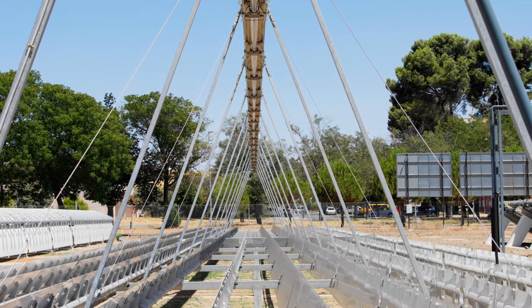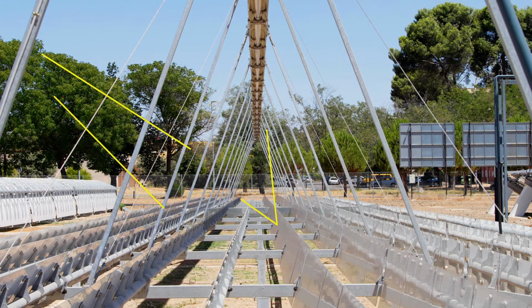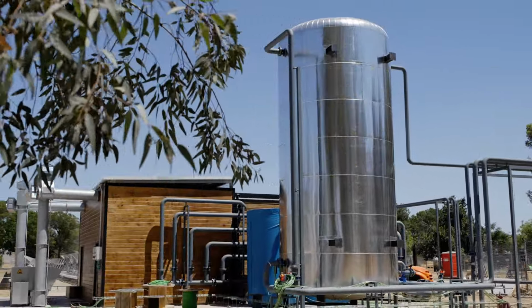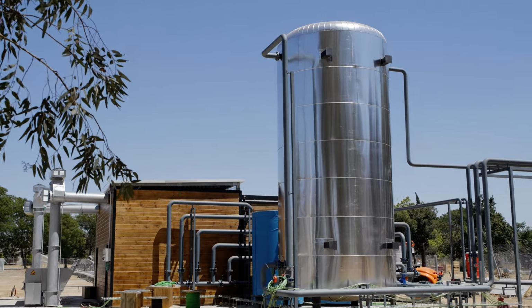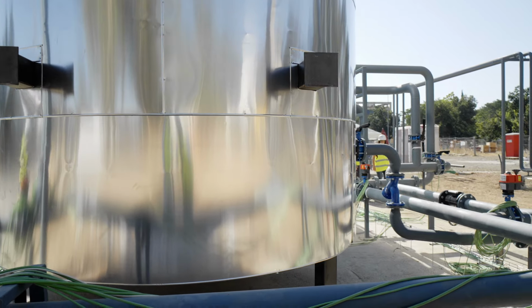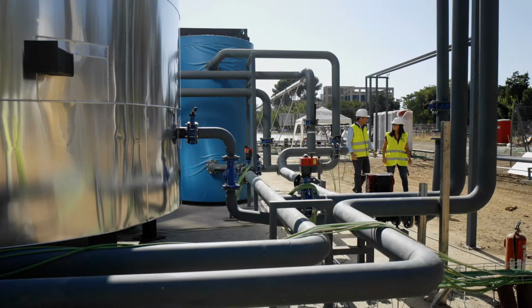The Fresnel collectors, for example, use flat mirrors to concentrate sunlight onto a central tube filled with water. As the sunlight hits these mirrors, they reflect and focus the light onto a central tube. The water inside the tube heats up rapidly, and its thermal energy is then transferred to a 50,000-litre storage tank. This tank can keep the temperatures up to 95 degrees Celsius, hot enough for various uses, such as hot water for domestic purposes in nearby buildings or to power cooling systems.